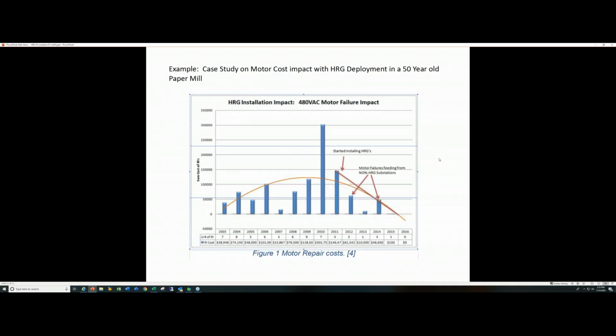The last slide I want to show you is some data taken from about 2003 to 2016 as we were deploying the HRGs. Basically over here, this is the sum total cost of motors, motor failure impact, and basically this motor cost was how much does it cost to rewind a motor and how much downtime we incurred. I found out from taking this data and looking at it over this many years that when a motor faulted, there was significantly less damage within the motor. Sometimes you could just get away with baking dips and you're up and running, and maybe some regular T-lead rewinds and you're up and running again, versus a total restoration, rebuild, bearing damage, etc., and so forth.